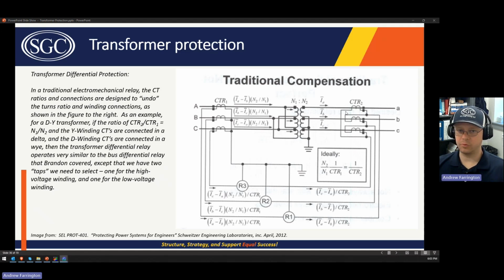And if you do that correctly, then the phase shift for the currents seen by the differential relay will be undone by the CTs such that the currents can be directly compared, which is what we want. You also need to account for the fact that these CTs are connected in a delta so that the current seen by the relay is going to be the square root of 3 higher than the actual phase current.